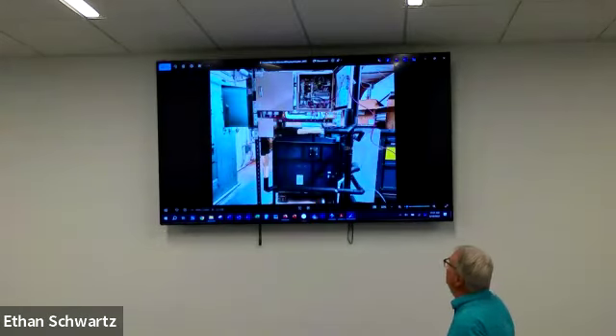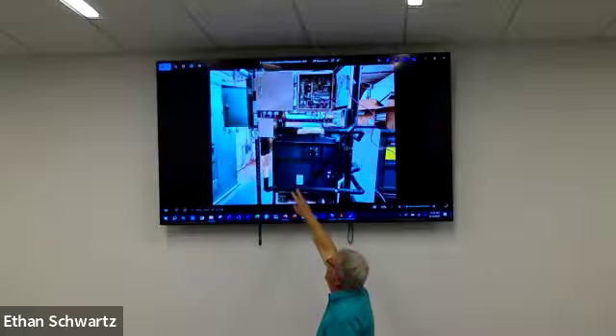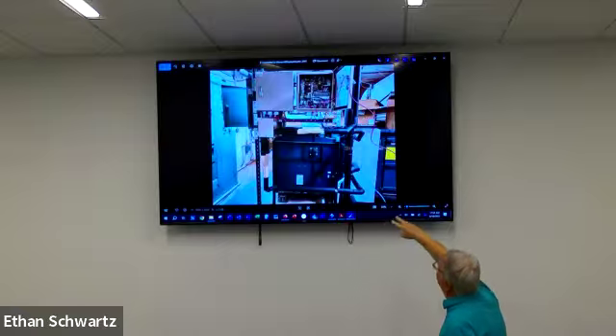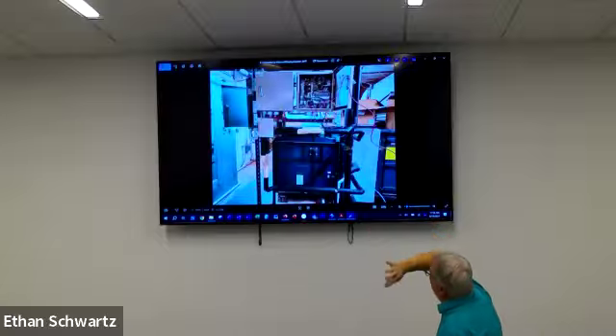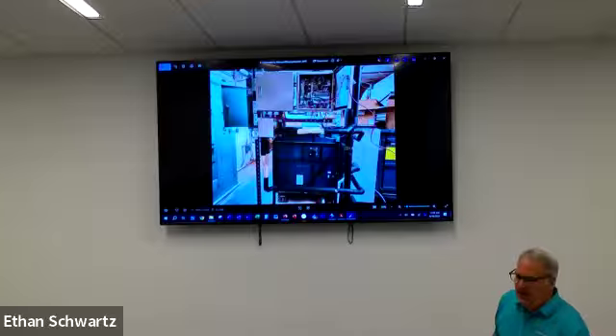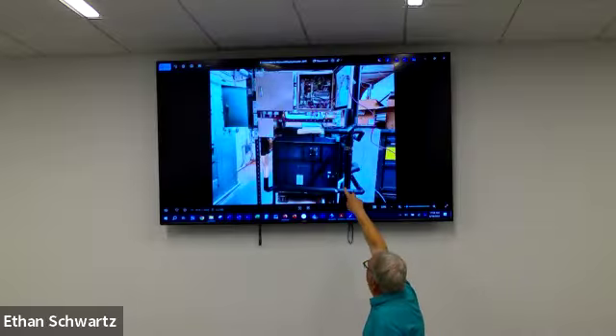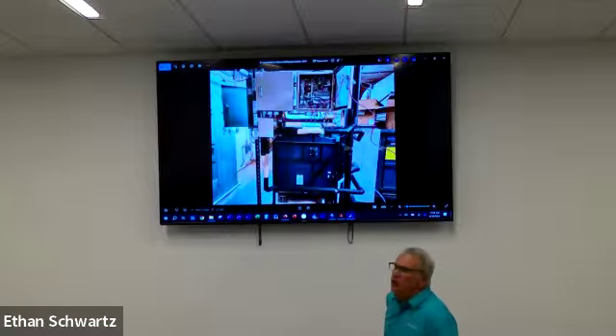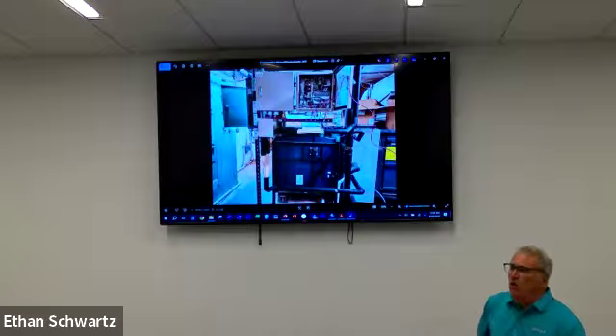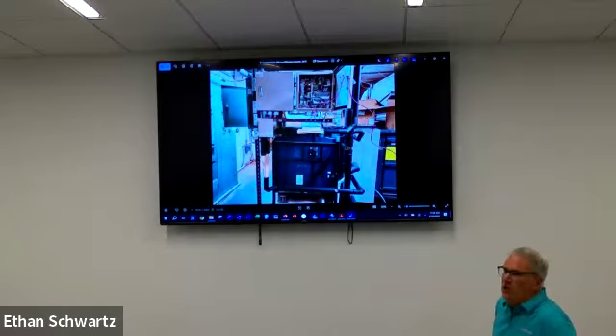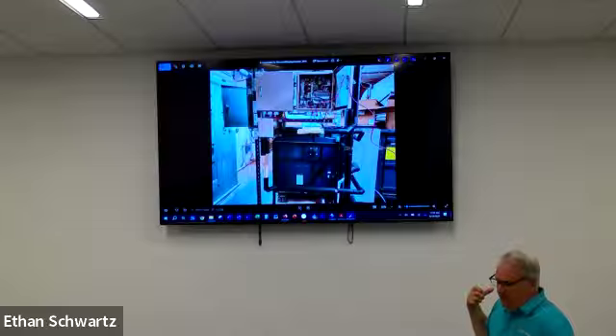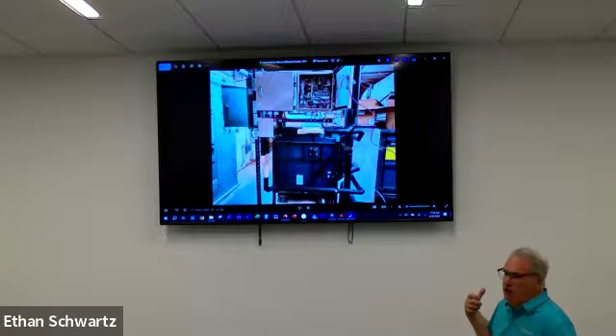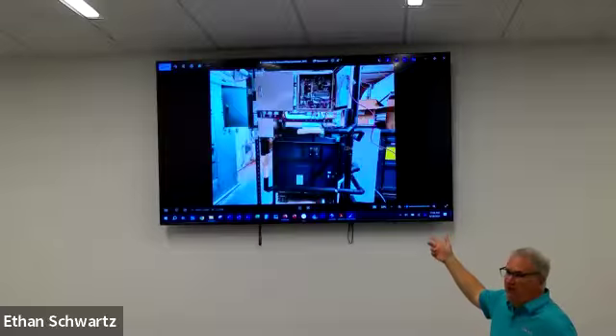All right, so on this particular application, all that old stuff went out. There's our EEV kits, and there's actually 2 coils, so 2 kits going to 20 tons each. The black cables coming out are the thermistors that go on the inlet and outlet of the coil.